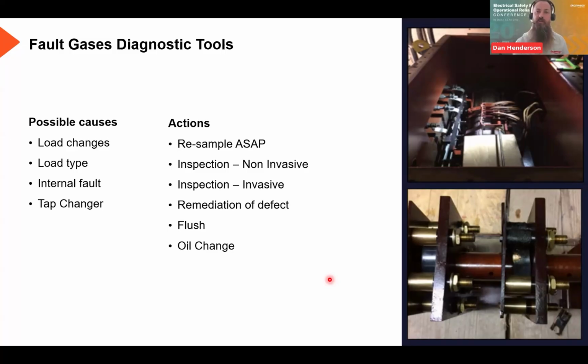There's an internal fault within that transformer that's causing that. But this is a common thing where certain vendors will just change your oil, which is quite a significant cost, and obviously it doesn't fix the issue. So make sure you understand the issue before you conduct your remediation of changing your oil out.